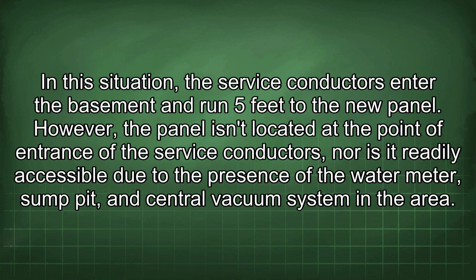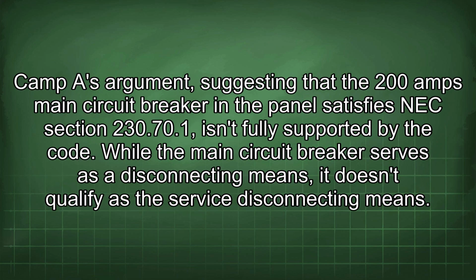In this situation, the service conductors enter the basement and run 5 feet to the new panel. However, the panel isn't located at the point of entrance of the service conductors, nor is it readily accessible due to the presence of the water meter, sump pit, and central vacuum system in the area. Camp A's argument, suggesting that the 200 amps main circuit breaker in the panel satisfies NEC Section 230.70.1, isn't fully supported by the code.